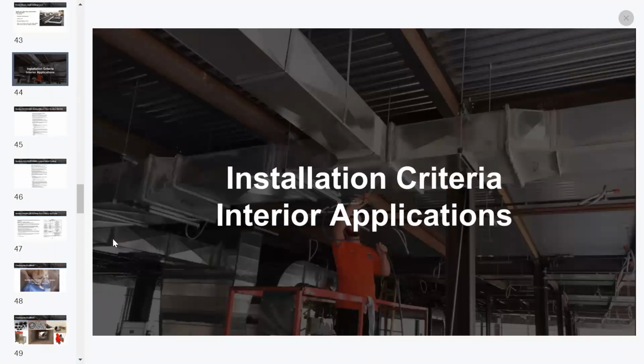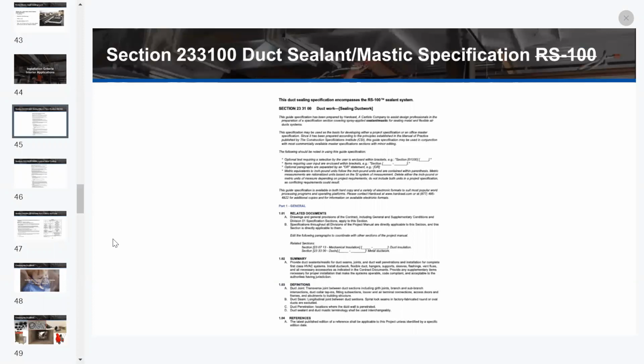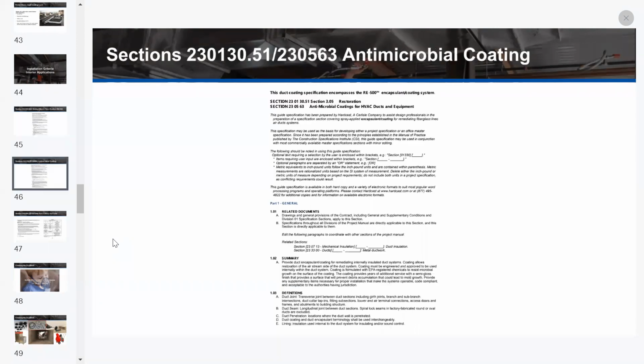So let's talk about some installation criteria for interior applications. There's section 233-100, which covers duct sealant mastic specifications. Just like you have specifications for exterior sealing, there are specification requirements for interior, or the air side. The air side should have full detail on the safety of the product and emissions once cured, due to the additional exposure through the building.